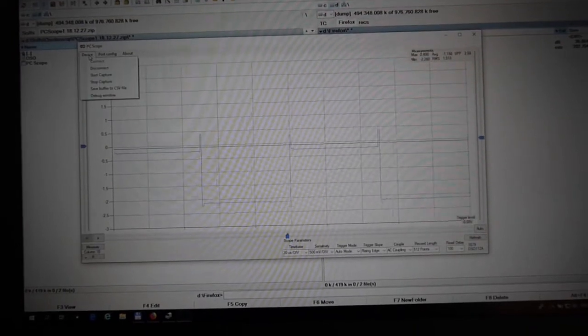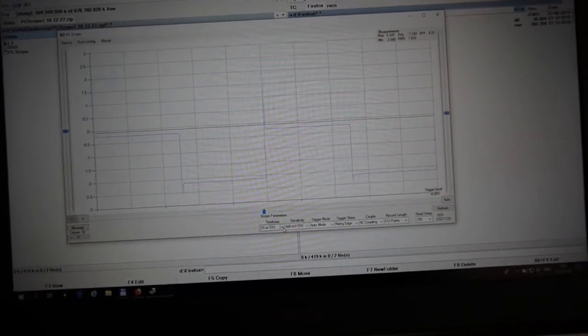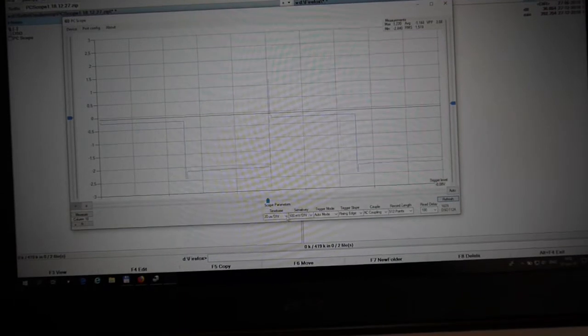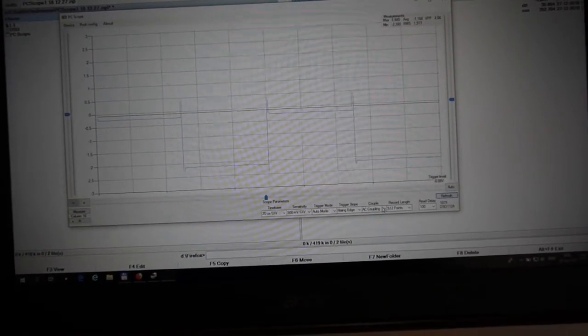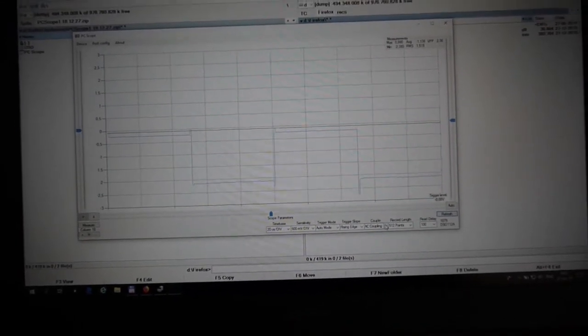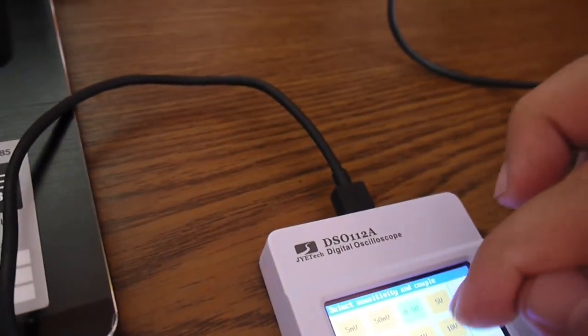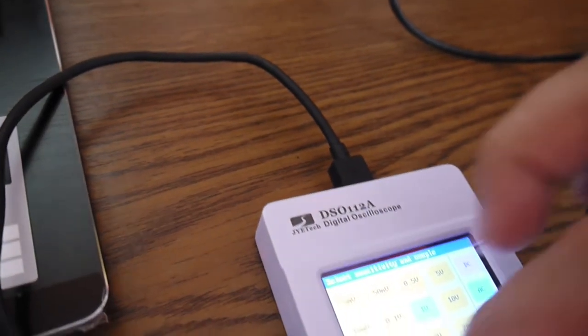The bad point is that you can't change anything from here, like sensitivity or time base or trigger mode or AC coupling, DC coupling and stuff like this. To do all these changes, we have to go back here and push exit, then go and do the adjustments.